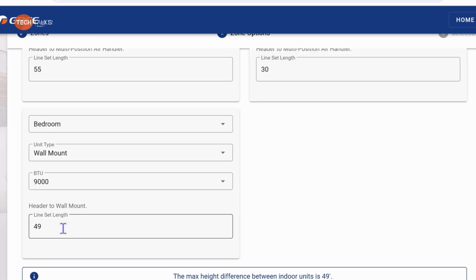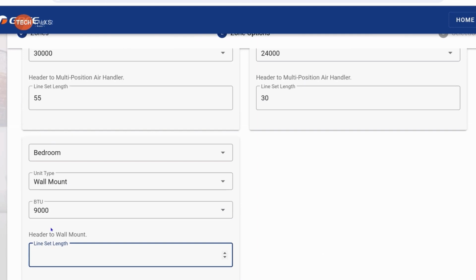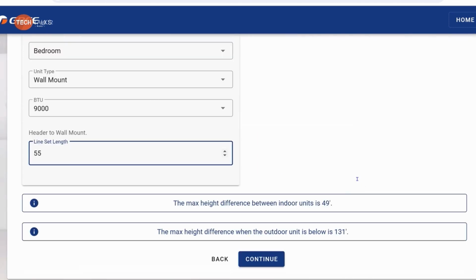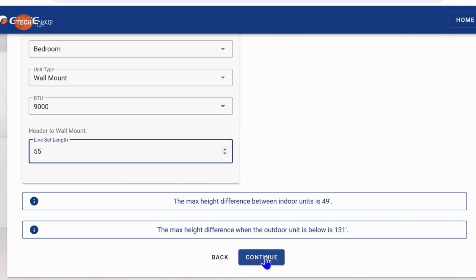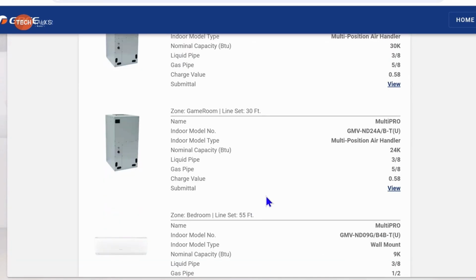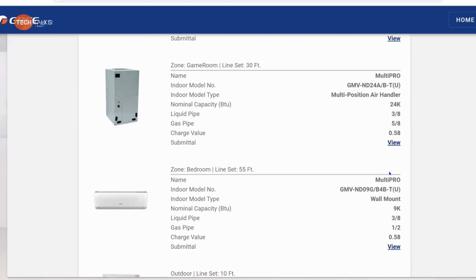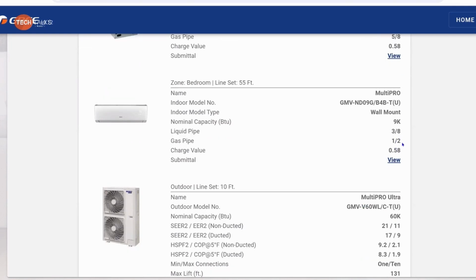This wall mount, I got it at 49 feet. I'm going to change this to 55 feet. Continue. Now, look what it did. Now, my line set is 3/8, half inch. It upsized the liquid line from 1/4 to 3/8, and it upsized the suction line, or the gas line, from 3/8 to half. And our multiplier for refrigerant changed to 0.58 because now we got a 3/8 pipe.